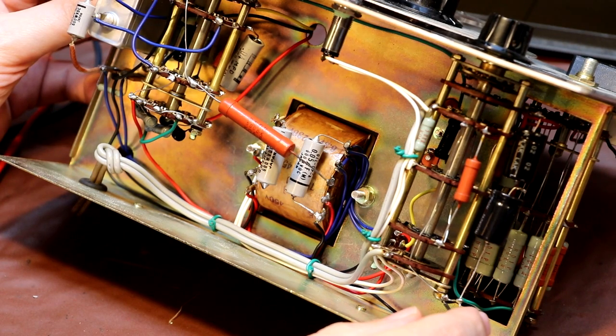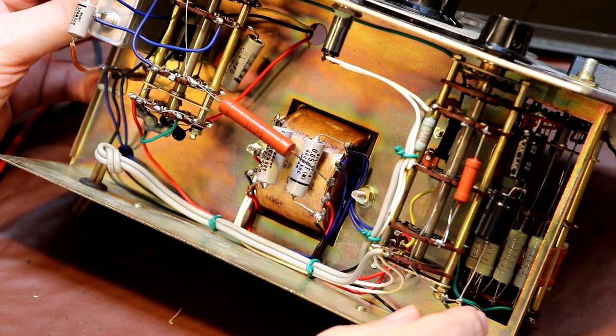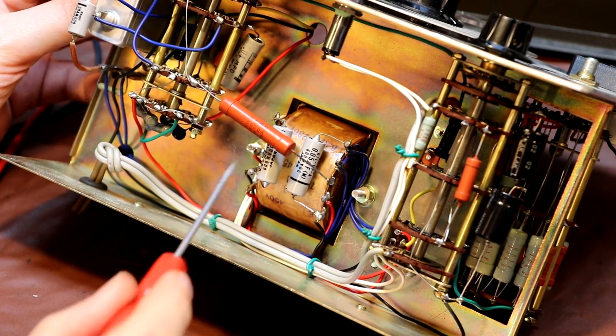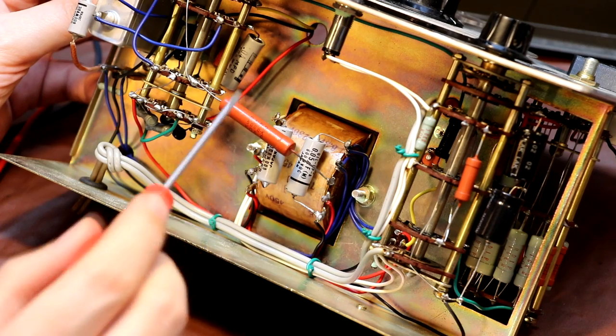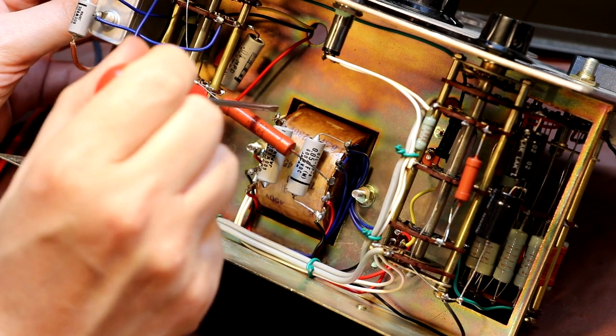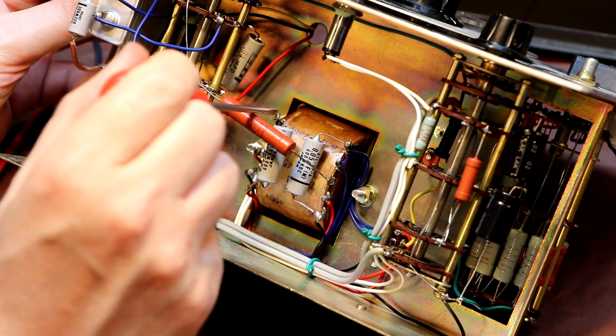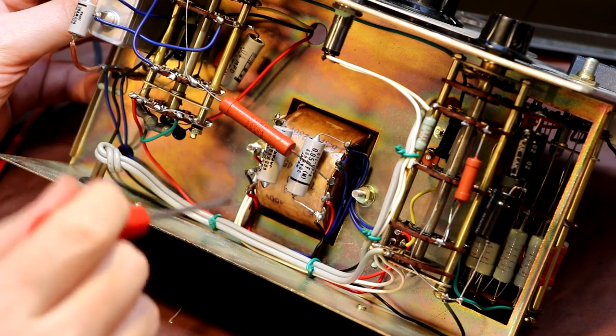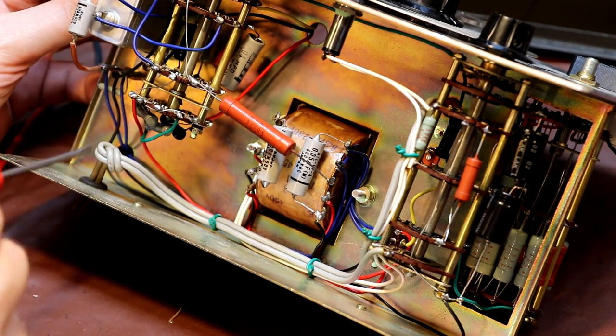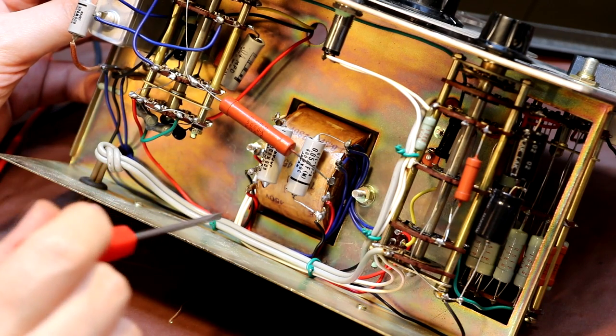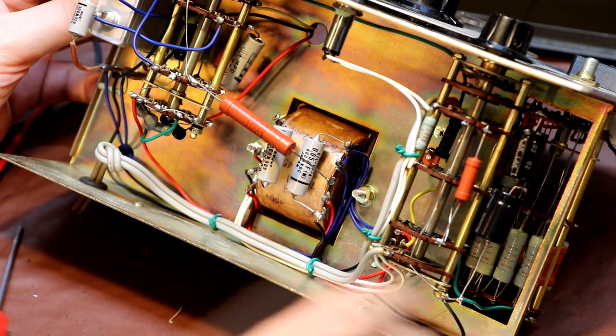but unfortunately I've been a little bit stumped. Now the problem that I've come up with is there's a capacitor here which is actually connected between the live side, so the actual supply, the mains 230 volt supply, and it's connected between the live terminal of the transformer and the chassis of the piece of equipment.